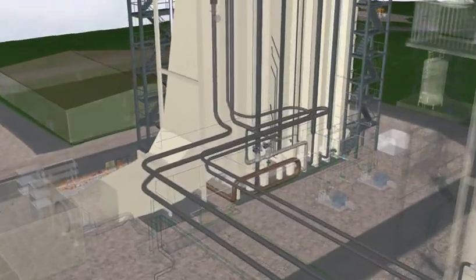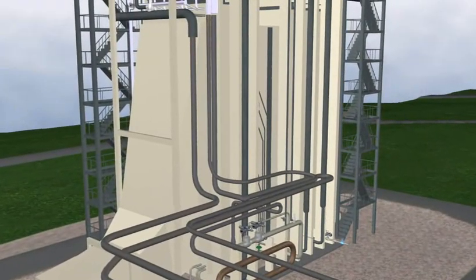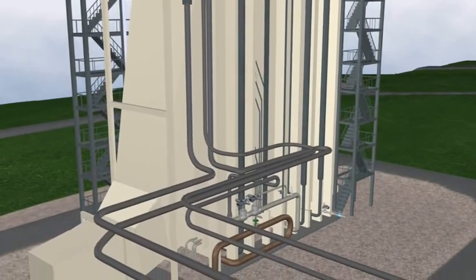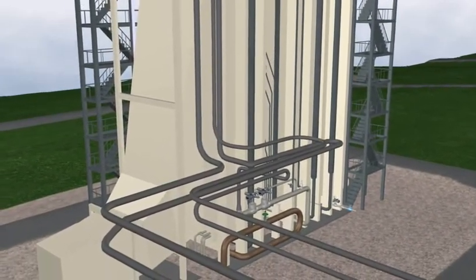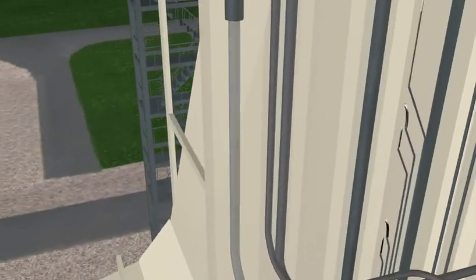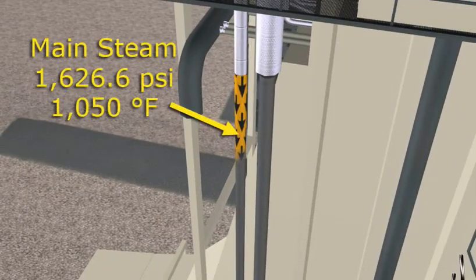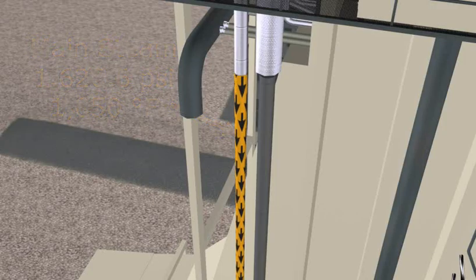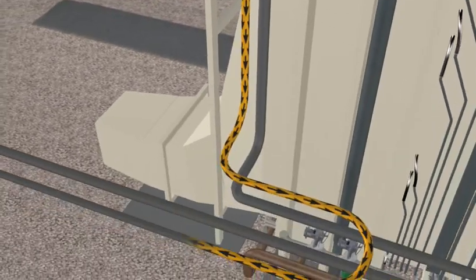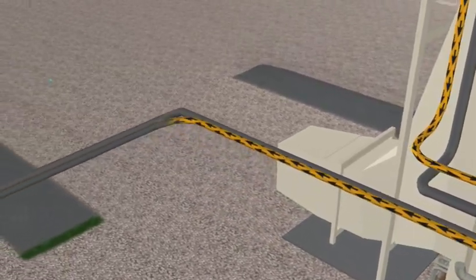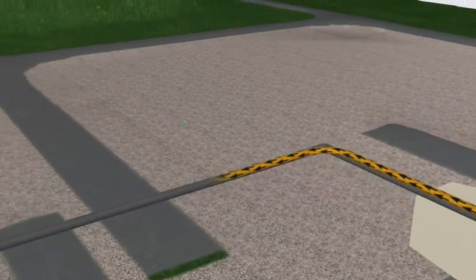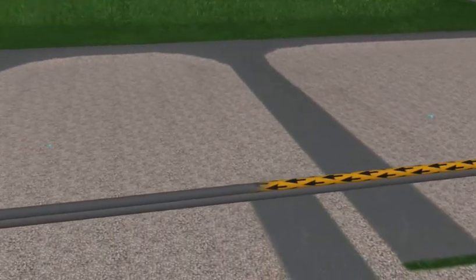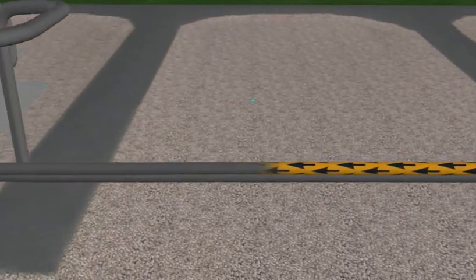The steam flows to the steam turbine through three steam lines. These steam lines operate at different temperatures and pressures. Main steam runs at 1,626.6 pounds per square inch absolute at 1,050 degrees Fahrenheit. Main steam may also be referred to as high pressure or HP steam.